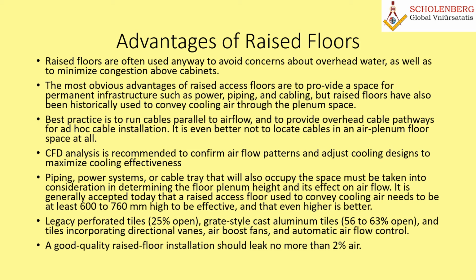Well, there are several advantages of the raised floor as far as data centers are concerned. The most obvious advantage of a raised floor is to provide space for permanent infrastructure such as power, piping, cabling. But these are just some of the advantages. Another is that it acts as a plenum for air distribution. So we can pump the air into this raised floor. The air travels within the plenum, it gets pressurized, and then the air comes out of the perforated tiles which are fixed on the data center floor, and it can be distributed based on the density of machines.